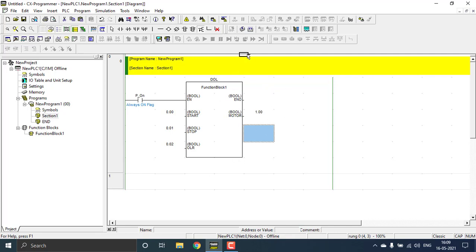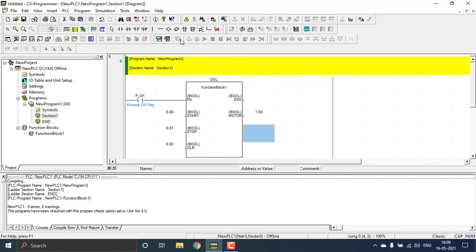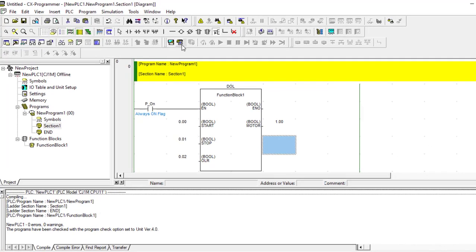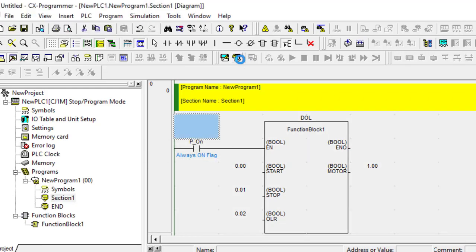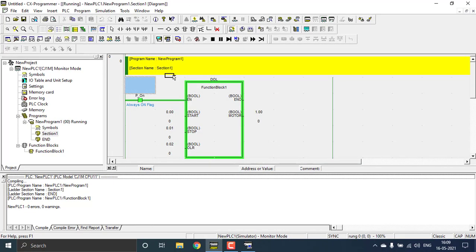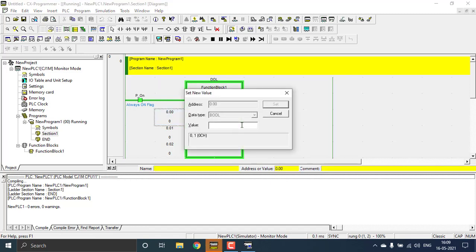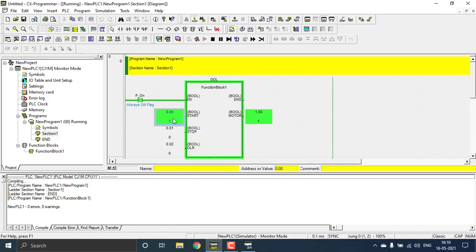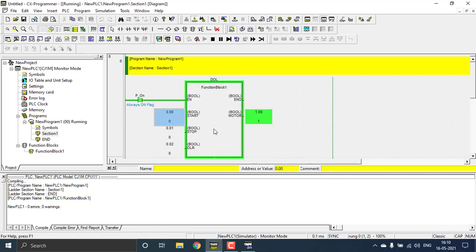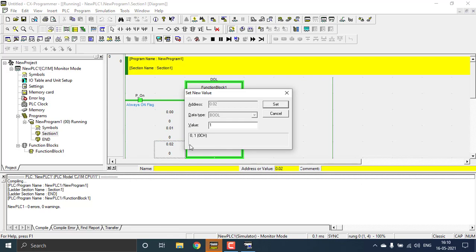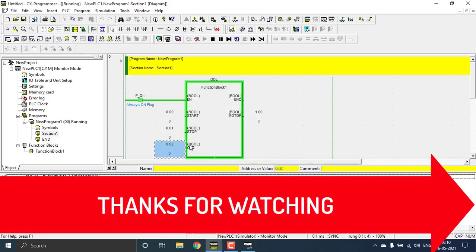We've completed the program. Compile the project — you can see there are no errors and zero warnings. Start the online simulator to go to online mode. Test the start and stop buttons: press Enter, input value 1 to press the start push button, then enter 0 to release it — it is still providing the output, showing the latch is working. Pressing the stop button or the OLR overload button will stop the motor. That confirms the DOL function block is working in the OMRON PLC.